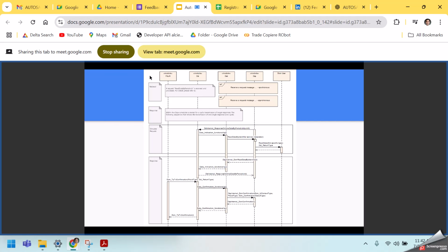Another case will be delay based. Let's say we set delay as 25 milliseconds, and it will check whether the event occurred, and after 25 milliseconds it's still in the active state. Then we will store that snapshot data. So it works like that.